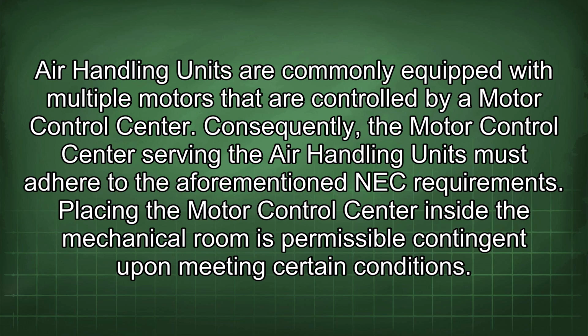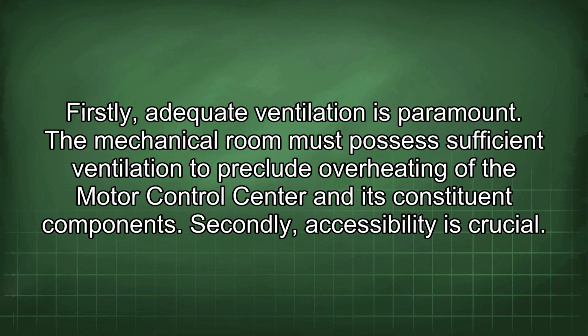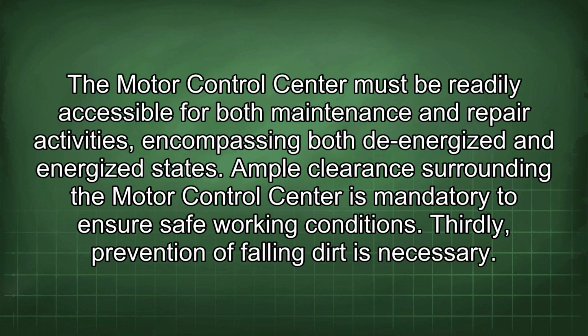Placing the motor control center inside the mechanical room is permissible contingent upon meeting certain conditions. Firstly, adequate ventilation is paramount. The mechanical room must possess sufficient ventilation to preclude overheating of the motor control center and its constituent components. Secondly, accessibility is crucial. The motor control center must be readily accessible for both maintenance and repair activities, encompassing both the energized and de-energized states. Ample clearance surrounding the motor control center is mandatory to ensure safe working conditions.